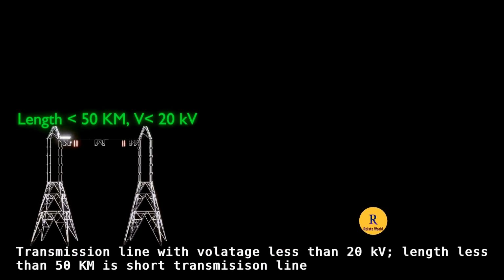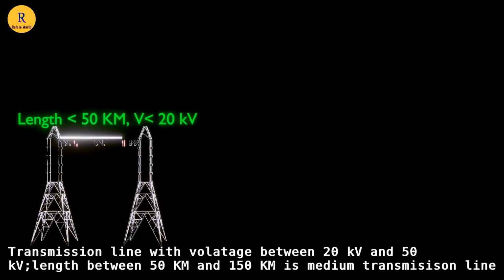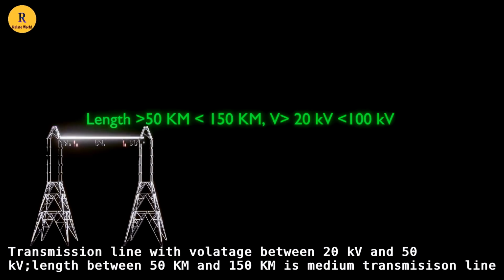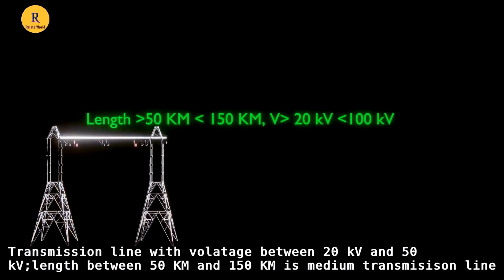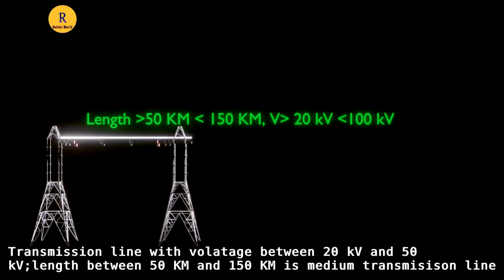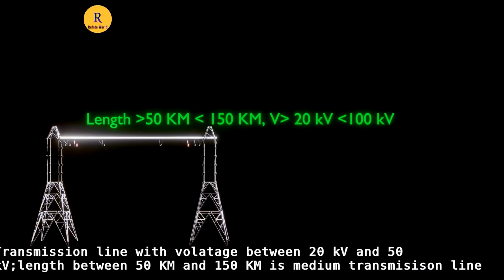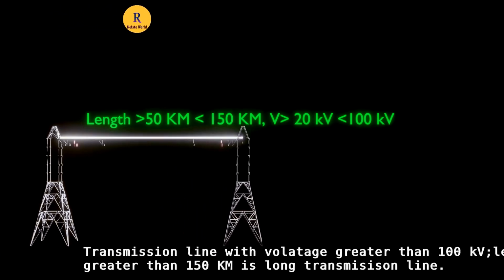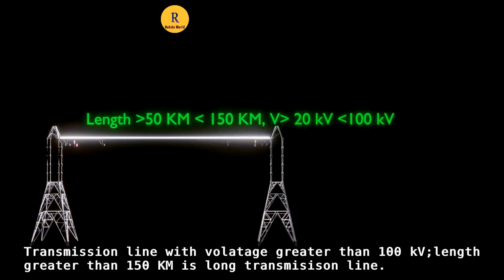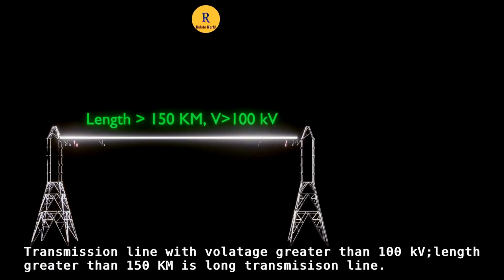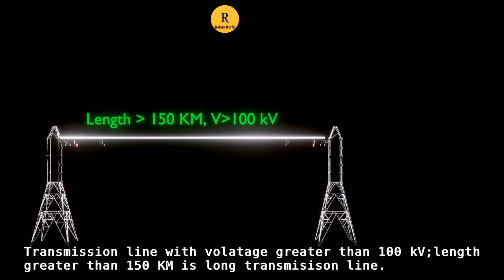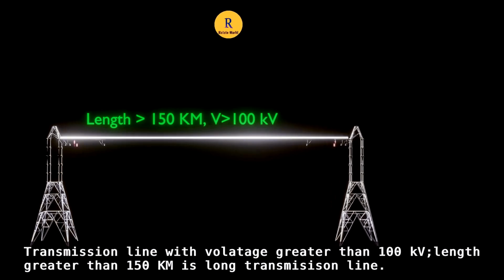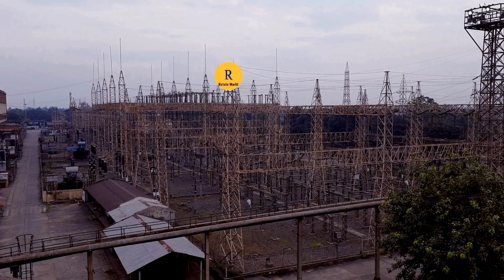A transmission line with voltage less than 20 kV and length less than 50 km is a short transmission line. A transmission line with voltage between 20 kV and 50 kV and length between 50 km and 150 km is a medium transmission line. A transmission line with voltage greater than 100 kV and length greater than 150 km is a long transmission line.